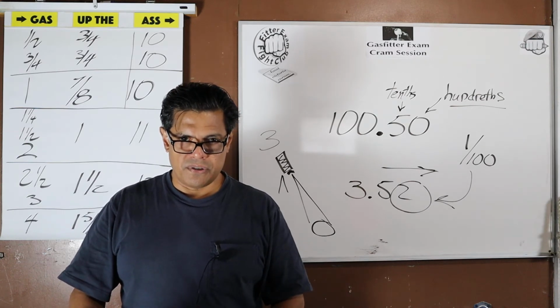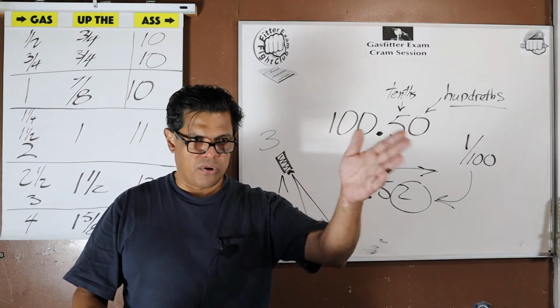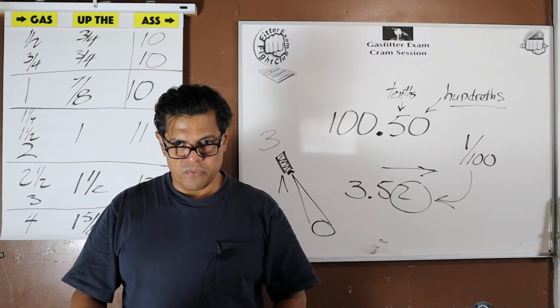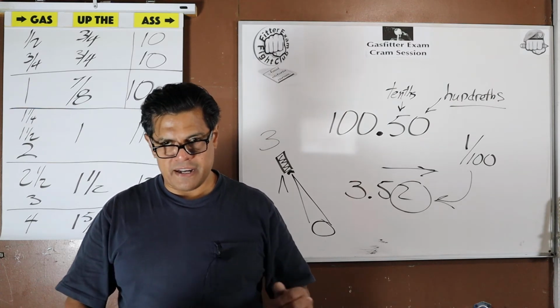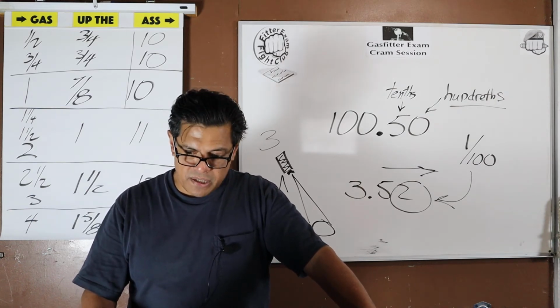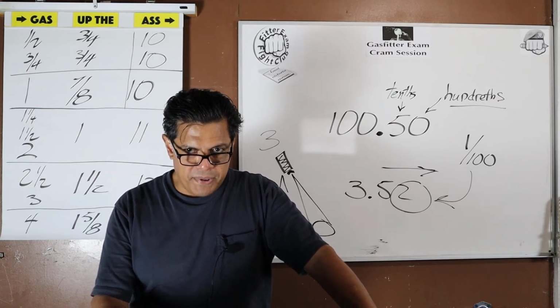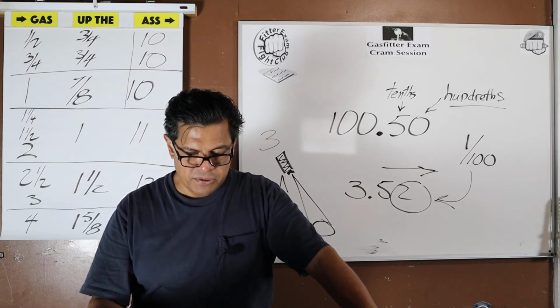Okay, it's a 2-inch horizontal branch, and then we're taking off 1.25 risers. Is it in the public corridor section? Then code says we're going to be welding 1.25 and 2-inch piping on a half psi system, where we knew that was going to happen if we were working with anything over 5 psi, but look what can happen in the code. If you're not paying attention, you're running that piping and then you have to rip it all out because you didn't realize, if it's in the public corridor, it has to be welded.